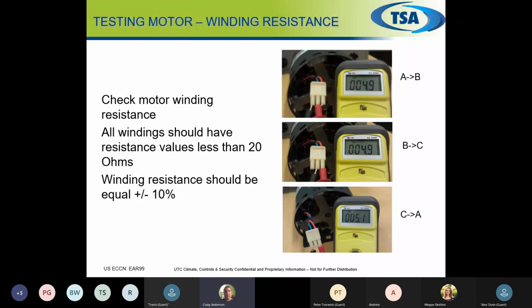We can also do a resistance check on the motor itself from A to B, B to C, C to A. We're just switching up the connections. Windings should be equal. Resistance values less than 20 ohms is what we want. So each winding is like checking a compressor if you're in air conditioning. Each reading on this one, because we're dealing with a different motor, is like your mini split DC compressors. When we're testing them, our resistance values should be equal on that motor.